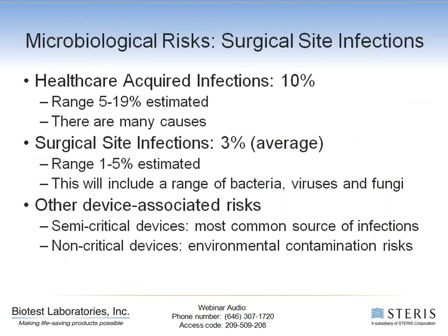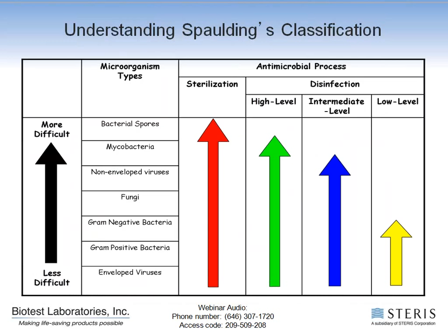This chart shows a range of microorganisms and their relative resistance to inactivation. It is generally considered that bacterial spores show the greatest resistance to inactivation, while enveloped viruses such as HIV or the much-discussed concern of the day, Ebola, are more easy to kill. The expectations for the various inactivation methods, such as sterilization and the different levels of disinfection, are shown and need to be considered during validation.